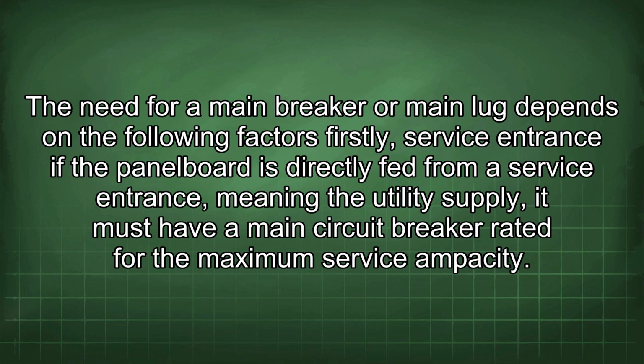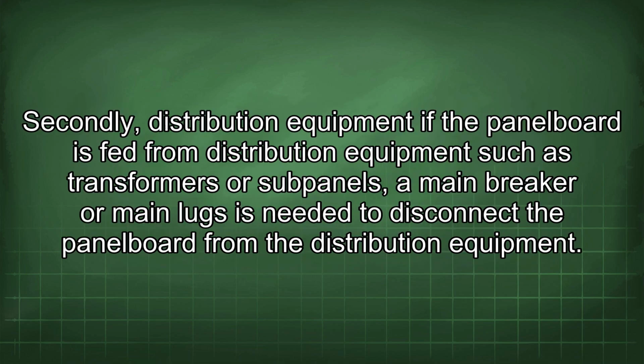Firstly, service entrance. If the panel board is directly fed from a service entrance, meaning the utility supply, it must have a main circuit breaker rated for the maximum service ampacity. Secondly, distribution equipment. If the panel board is fed from distribution equipment such as transformers or subpanels, a main breaker or main lugs is needed to disconnect the panel board from the distribution equipment.